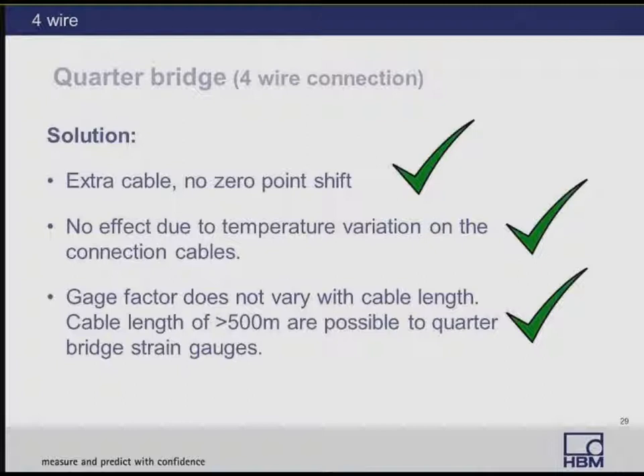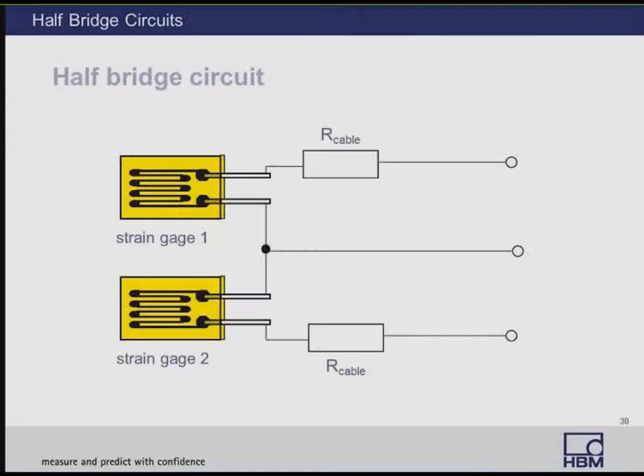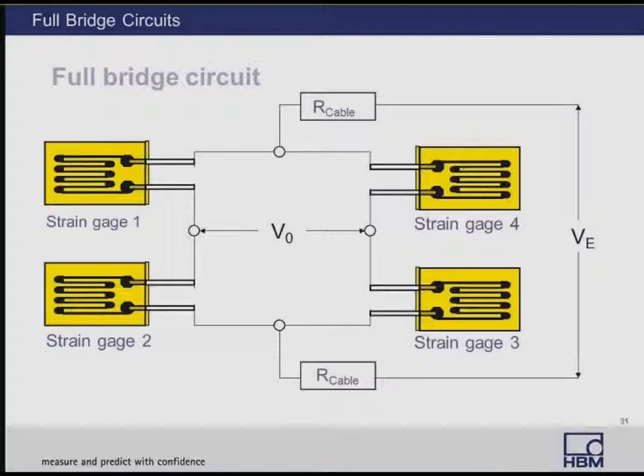Up to this point we have focused on quarter-bridge configurations. Many of these issues are lessened when using half or full-bridge configurations. In a half-bridge configuration, the minimum number of wires required is always three wires. Cable resistance is still a factor, and the same suggestions apply. The full-bridge circuit, on account of its favorable characteristics — larger measurement signals and automatic compensation of interference effects — is the preferred arrangement for transducer construction. It has the advantage that internal bridge wiring is short and symmetrical, all cables are identical in length and value, and the resistance of connecting wires is typically so small it can be neglected.